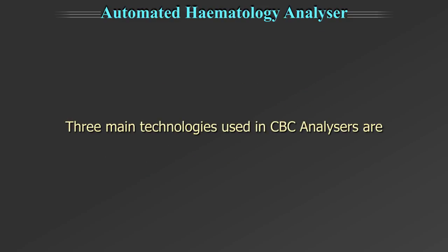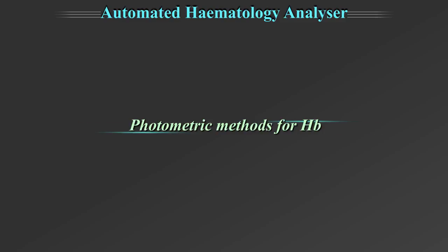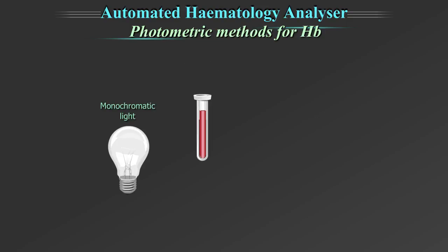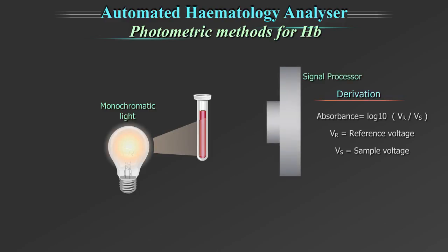The three main technologies used in hematology analyzers are: first, the photometric method for hemoglobin estimation. RBCs are lysed and the hemoglobin released is converted to a colored measurable compound. A monochromatic light from a light source is then passed through the solution.